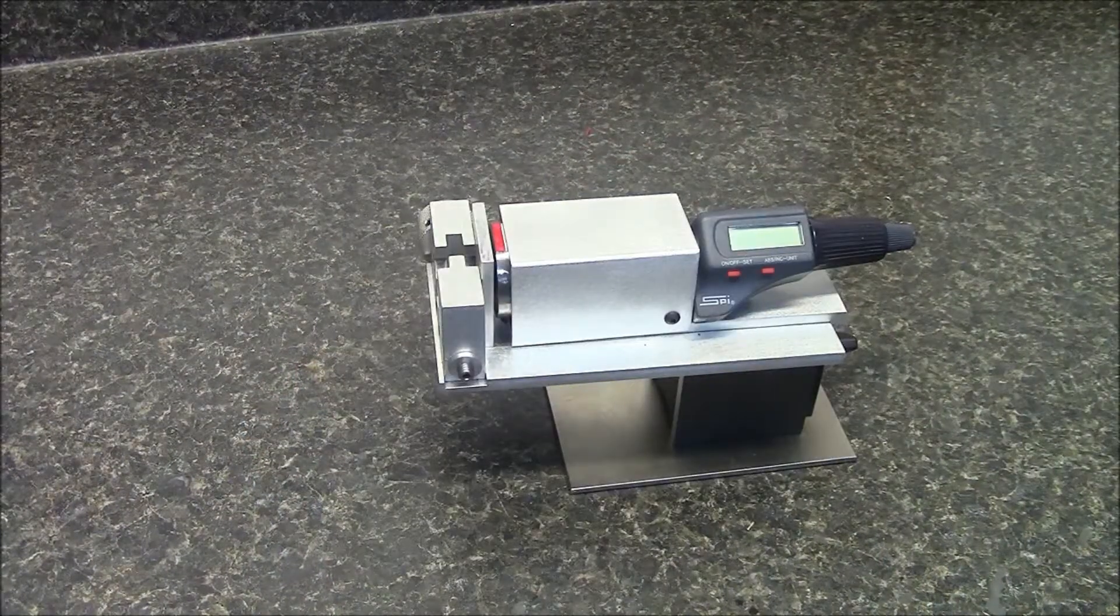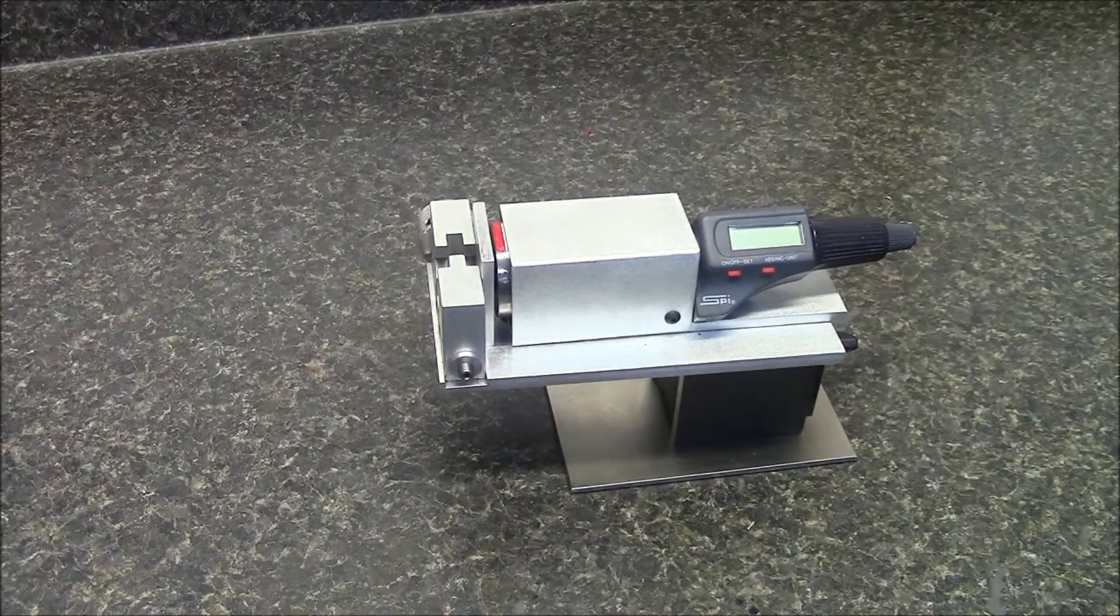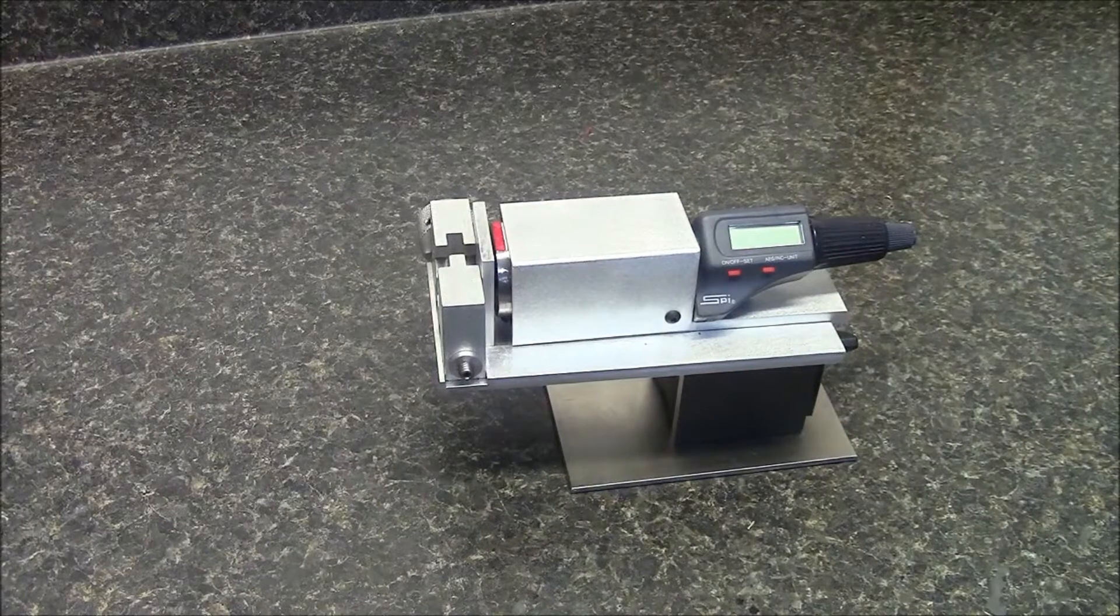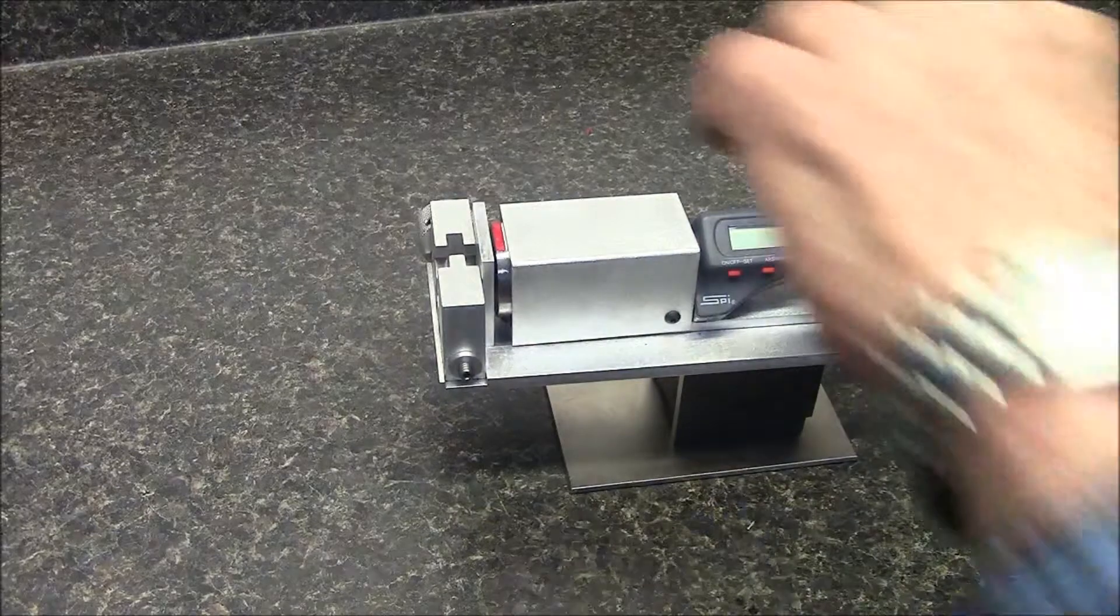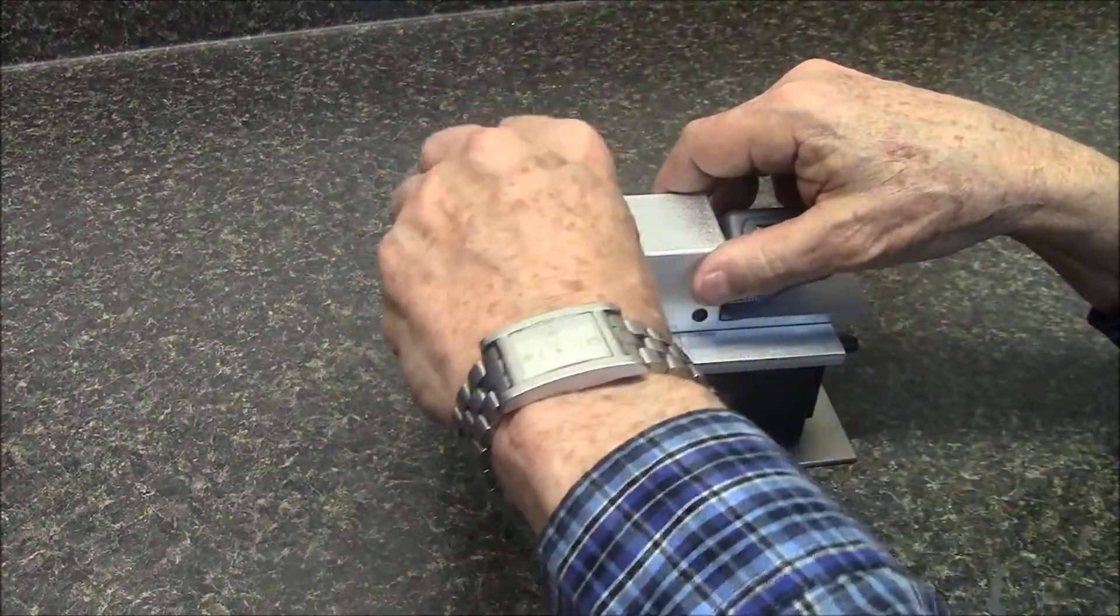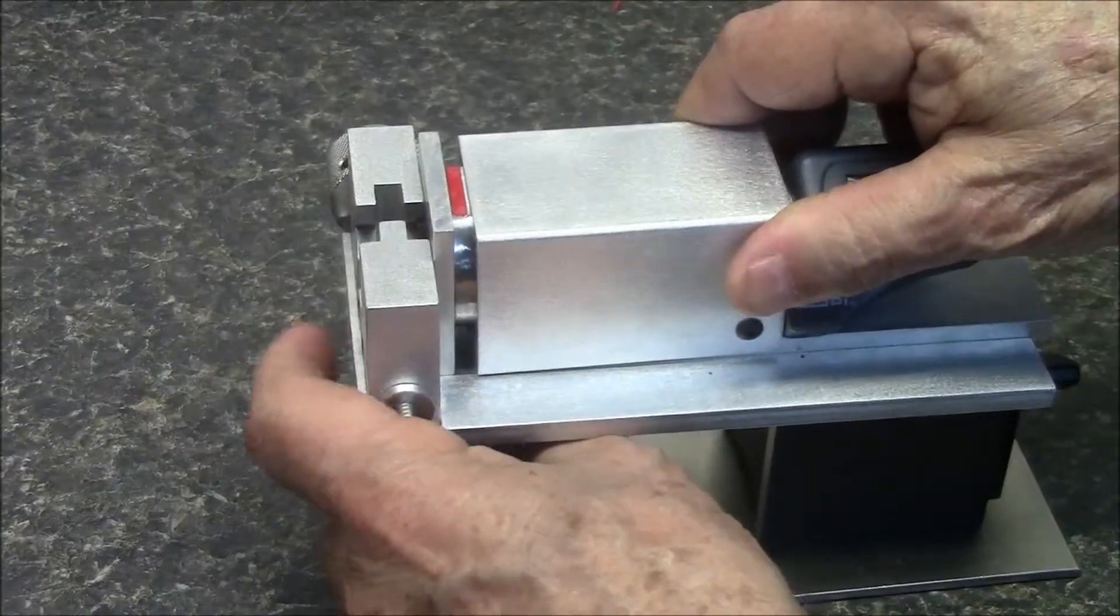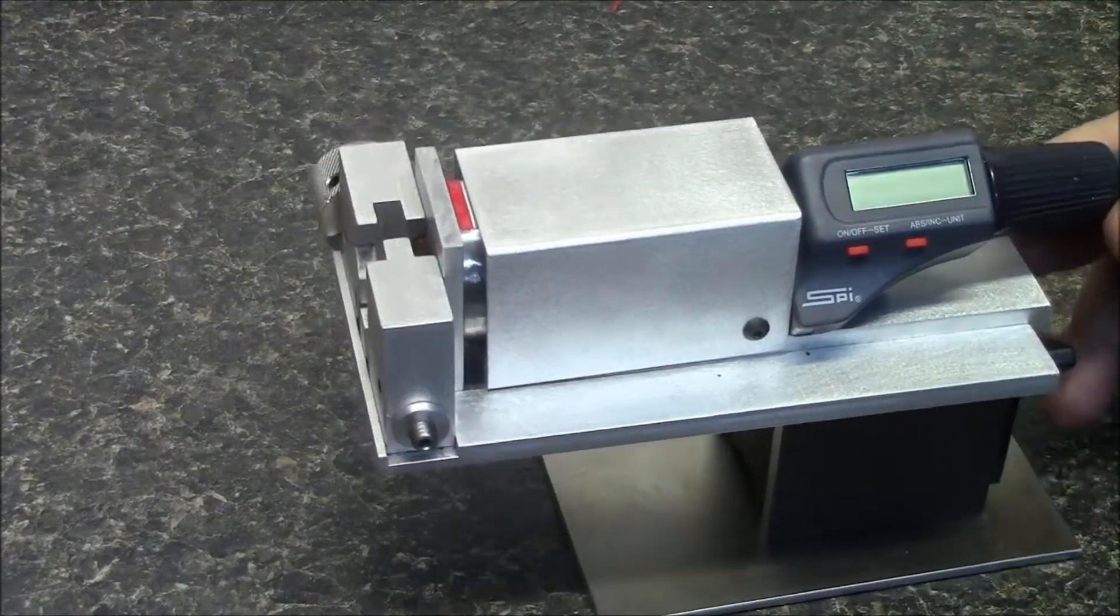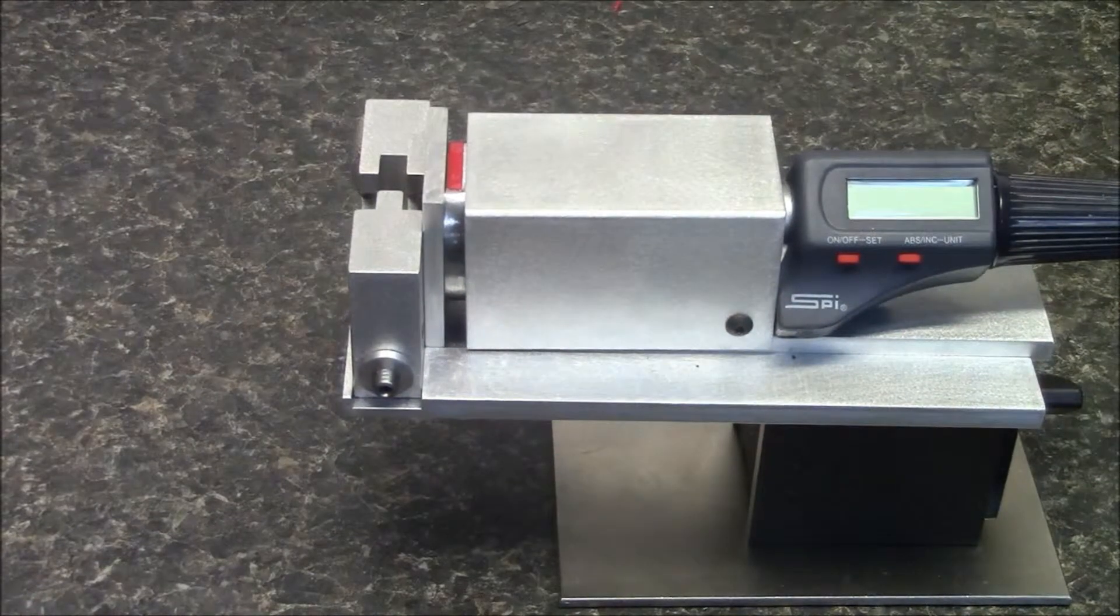If you suspect that the calibrator alignment has been damaged during shipment or handling, you can simply turn the support plate around to check that the target material is still perfectly aligned with the probe holder. As follows: turn this around, put it back in, close this, and lock it in place. Now you can look at it to see that it is absolutely parallel to the plate.